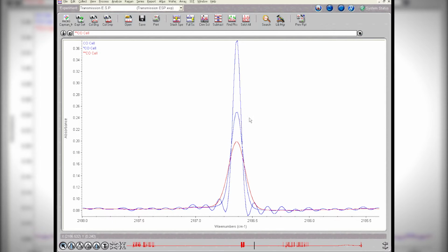So again, if we just compare them, the unapodized, you see very sharp peaks. As you apply apodization to this, the peak broadens. So the general rule of thumb, you're not going to be worried about apodization. Most of the time, the defaults that are set as part of the instrument are going to be totally adequate. The only time it's going to matter is when you switch over to a high resolution gas spectrum, such as this carbon monoxide spectrum, with very narrow peaks. These are on the order of about 0.08 wave numbers wide. So it's a very narrow peak.